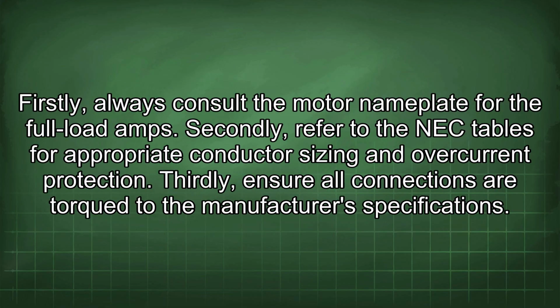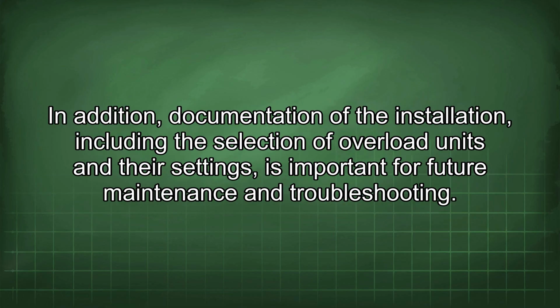Firstly, always consult the motor nameplate for the full load amps. Secondly, refer to the NEC tables for appropriate conductor sizing and overcurrent protection. Thirdly, ensure all connections are torqued to the manufacturer's specifications. In addition, documentation of the installation, including the selection of overload units and their settings, is important for future maintenance and troubleshooting.